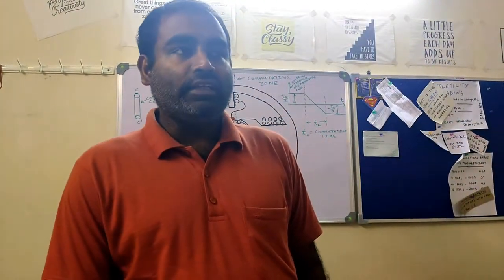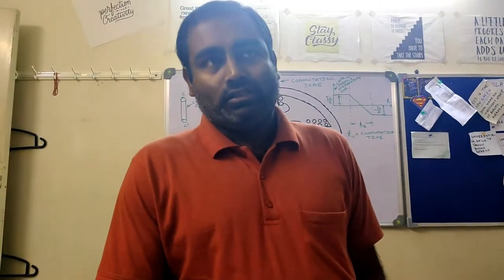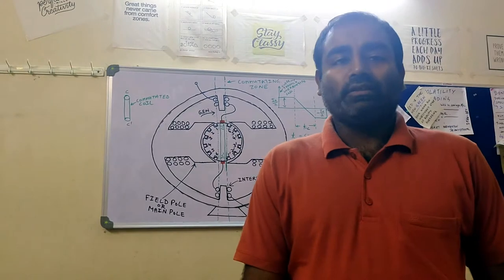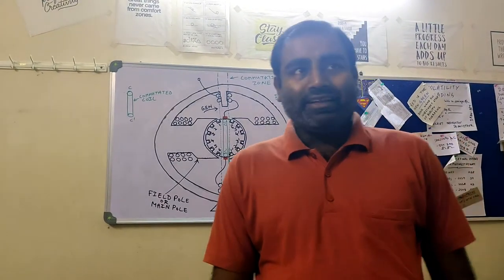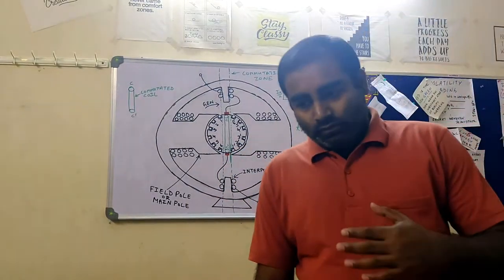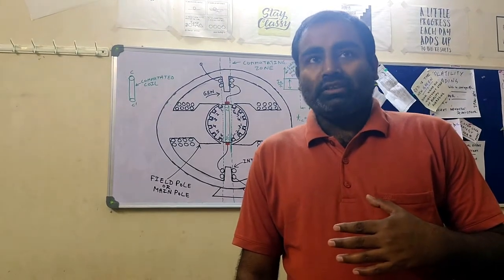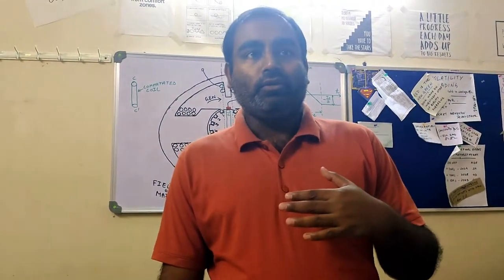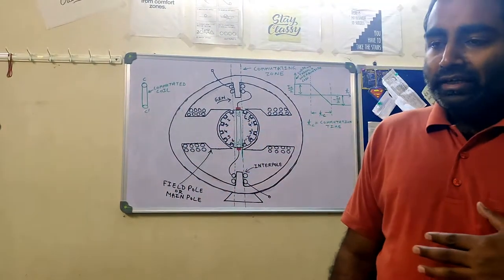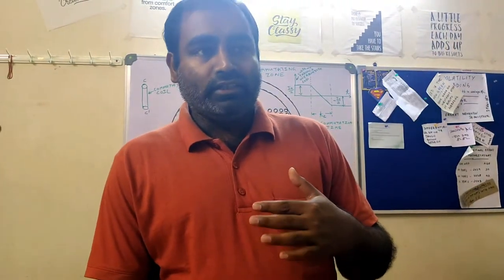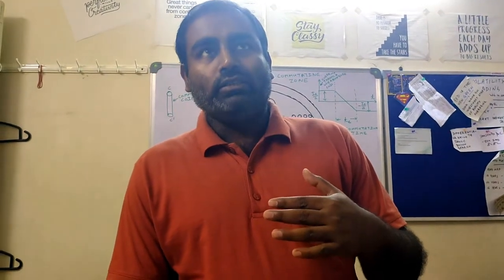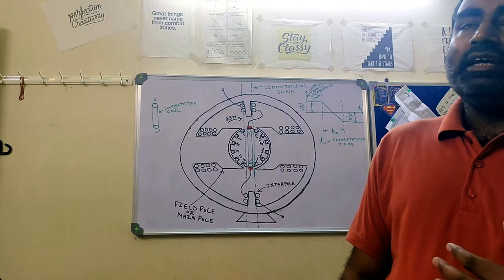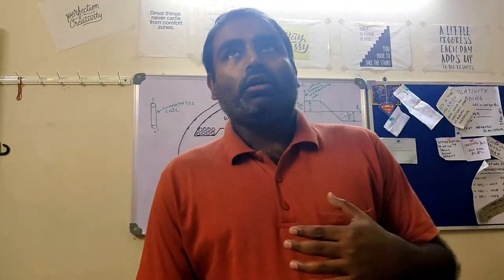This creates pits — small holes — on the commutator surface due to sparking. These pits attract dirt and moisture, so accumulation of dirt and moisture on the commutator surface creates a thin film of insulating layer. Because of that, the current density between that point where a thin film is created is very small or almost zero. So what happens is the current density at the other part of the commutator surface gets increased, which is very detrimental for operation of a DC machine.